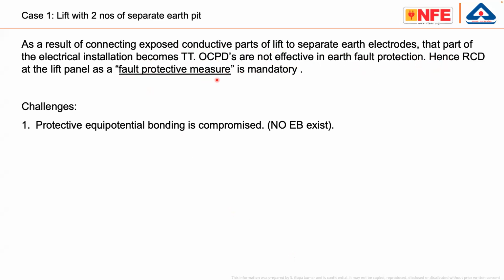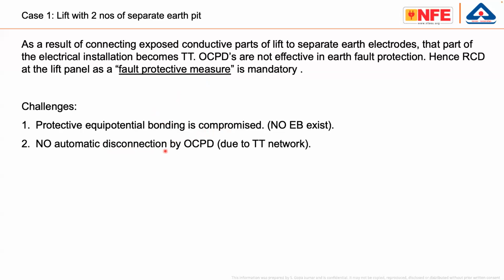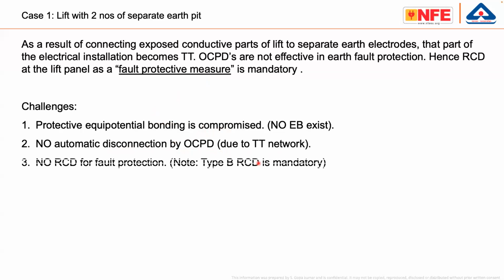That means you already have a 30 milliampere RCD to protect people in the car, whereas this is a different one. The challenges you should always keep in mind: protective equipotential bonding, which is a mandatory electrical safety requirement, is compromised. Automatic disconnection by OCPD is compromised in our installation, because if you test practically, there will be difficulty, as it is a different kind of TT system. No RCD for fault protection, and you should also consider that a type B RCD is mandatory. I delta of the RCD and the PE conductor current matter, because the lift has a variable frequency drive depending upon the size of the lift.